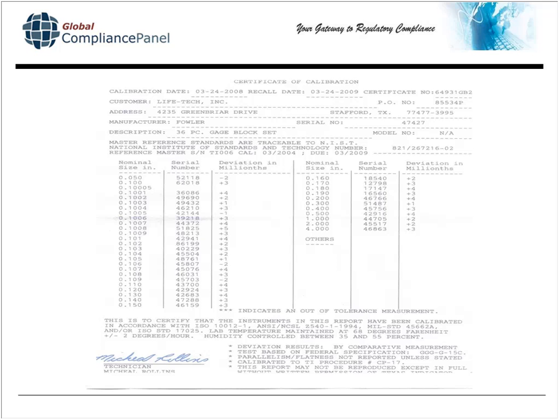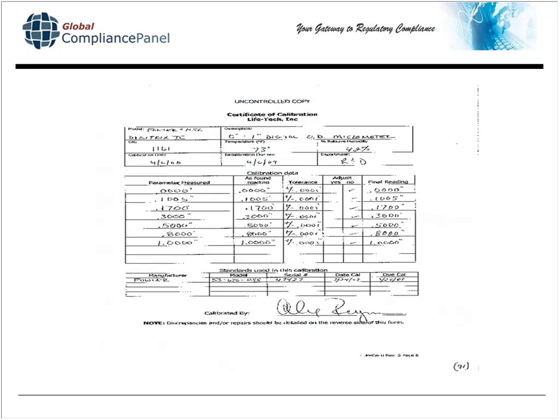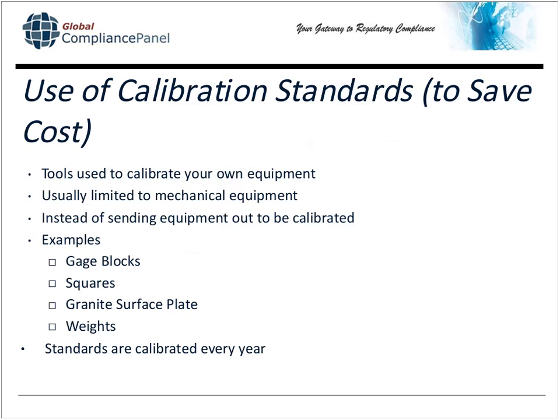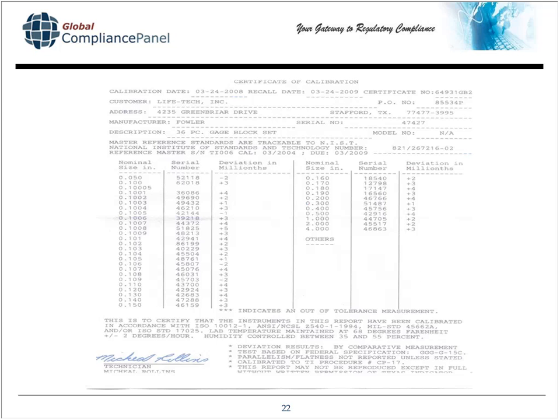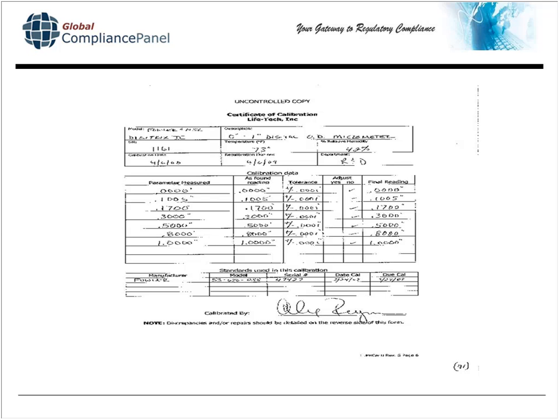The traceability here, if you look further on down, about 80% down, it references ISO 10012-1, the ANSI Z540, the MIL standard 45662. There's all sorts of traceability here. This is what you get when you send items out to be calibrated. These firms do it professionally, and in many cases, it's worth it to just get it out of your way. Other times, this particular micrometer, for example, the previous slide was gauge blocks. And what this micrometer is used for is it takes the gauge blocks on the previous slide and calibrates to them. This is a type of indirect traceability that I referred to previously.